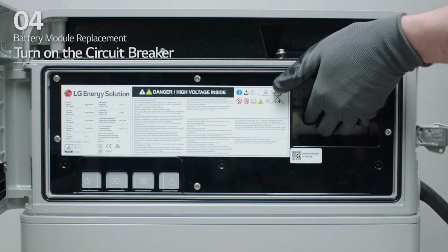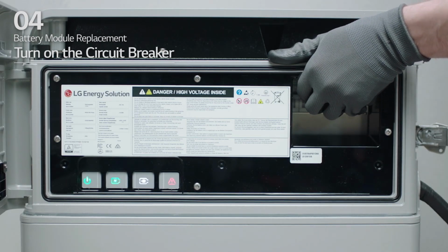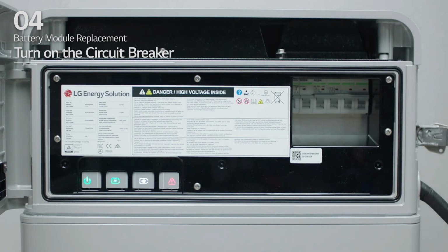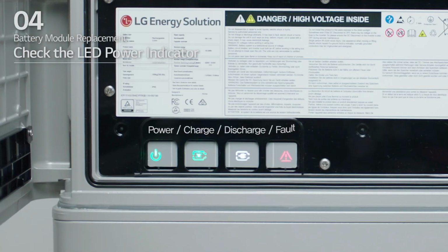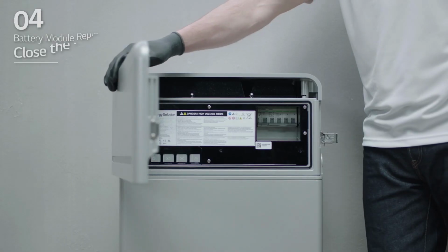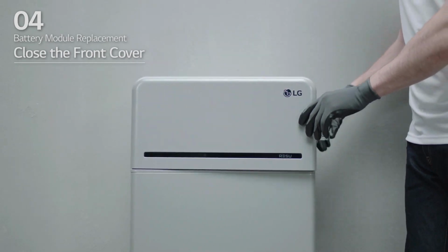Turn on the circuit breaker. Seconds after the circuit breaker is switched on, 4 LED indicators will light up. To ensure that installation has been done correctly, check that the LED power indicator is green. Finally, close the front cover and turn on the inverter.